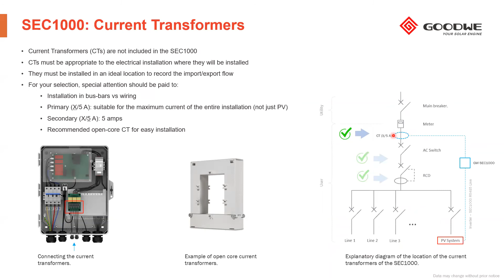So this is an example, explanatory diagram, right? The most important thing in the CTs is the location and the direction of the measurement, right? So you need to be sure that the location has to be upstream of the consumption and also of the PV system. It has to read import and export to the grid, right? That is one of the most critical things.